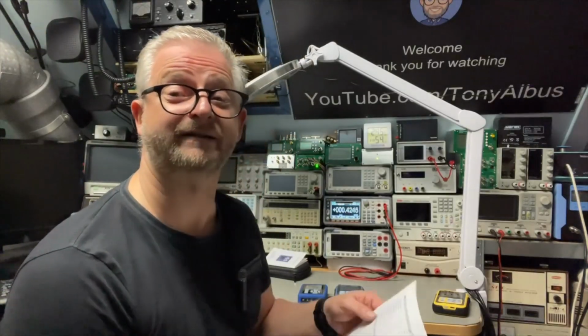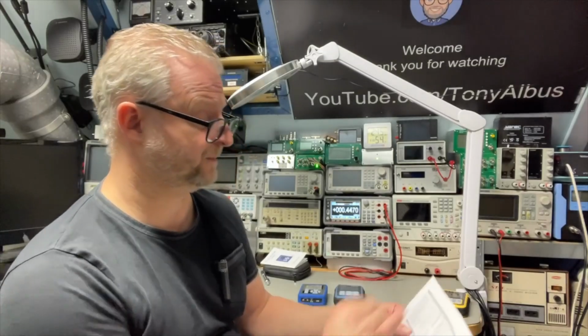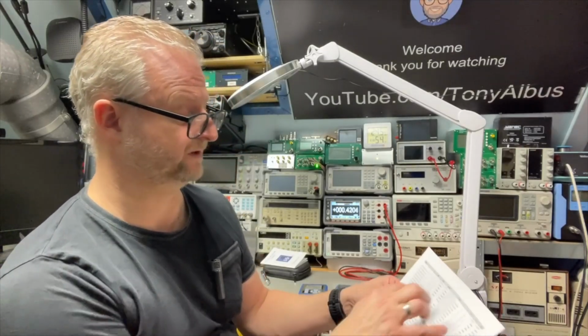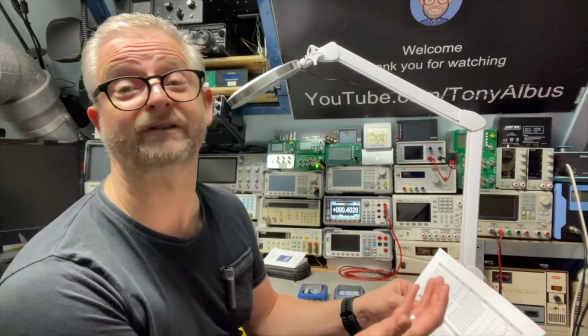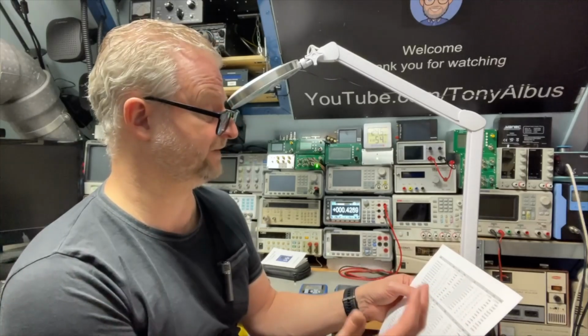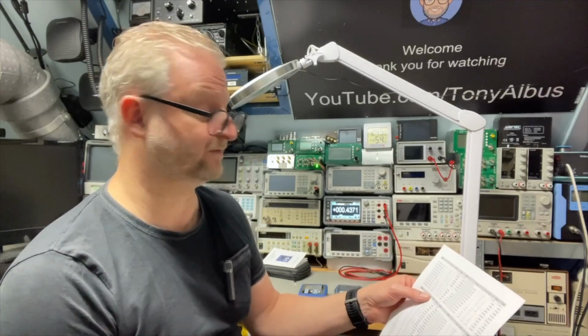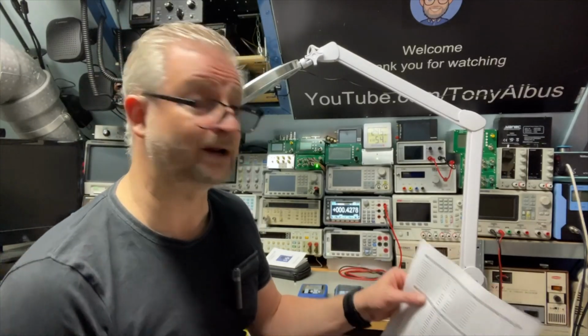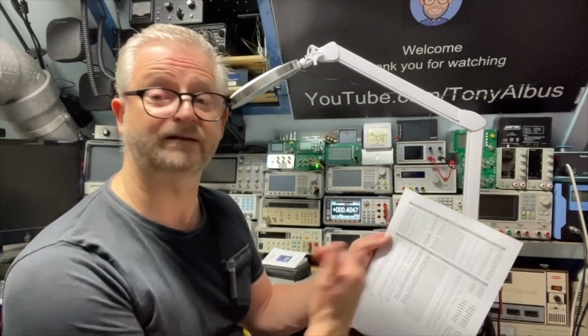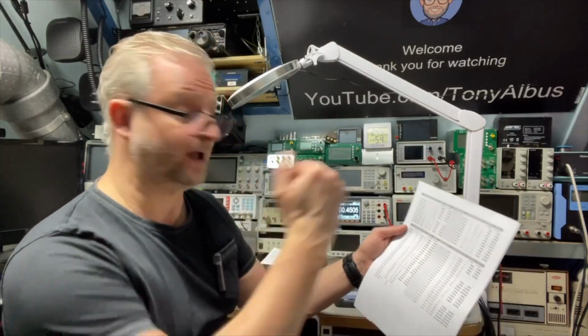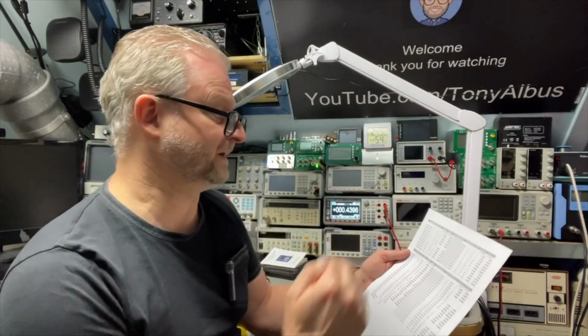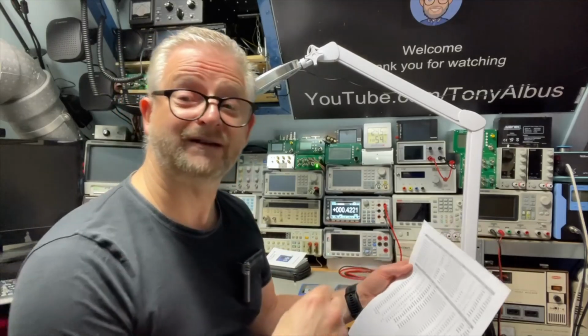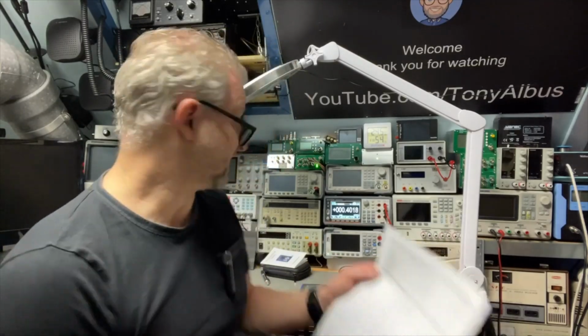So what I'd like to do now is some basic accuracy testing. I have a few voltages I want to test: 1, 2, 5, 10, 15, 20 if possible on that model, and for current 1, 4, 10, 15, 20 milliamps, and later resistance for the ones that have it. I'm just picking a few reasonable points, then we can compare before and after calibration.